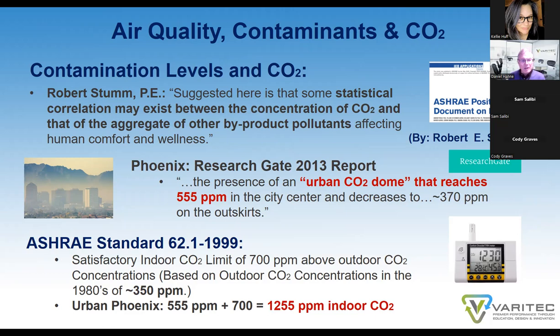Well, in 1999, ASHRAE Standard 62.1 offered this limit to CO2 concentrations in the built environment. It said that providing the built environment can maintain a CO2 concentration of 700 parts per million above the outdoor air CO2 levels, then that should be good enough to go. And that has been grandfathered into approximately 1,000 parts per million CO2, based on outdoor CO2 levels back in the mid 80s of about 350 to 370 parts per million. However, our CO2 concentrations are increasing. Urban Phoenix is now measuring in the realm of 555 parts per million. So if you use 62.1's guideline and add 700 to that value, you're now at 1,255 parts per million of indoor CO2.